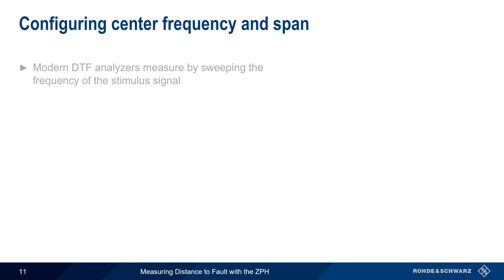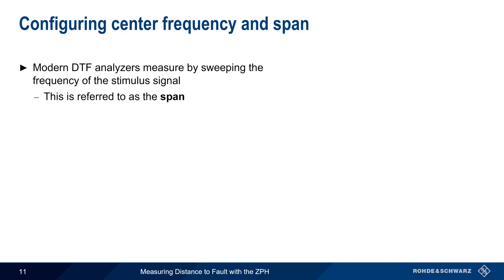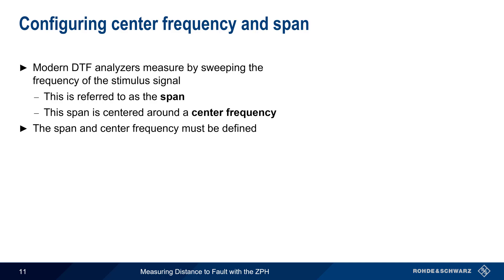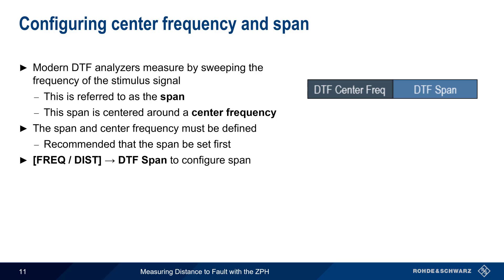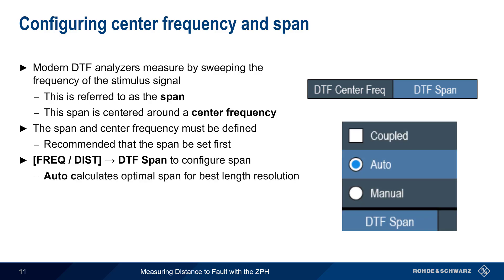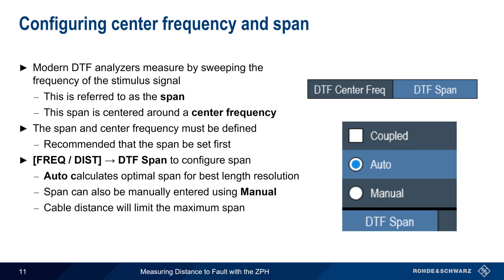Modern distance to fault analyzers measure by sweeping the generator over a frequency range, and this range is referred to as the span. This span in turn is centered around a center frequency. The span and center frequency must be defined, and in DTF measurements, the recommendation is to set the span first. Span is configured by pressing the Frequency Distance hard key, and then DTF Span. In most cases this can be left as Auto, which calculates the optimal span for the best length resolution, although span can also be manually configured. After span has been configured, use DTF Center Frequency to set the center of the span.